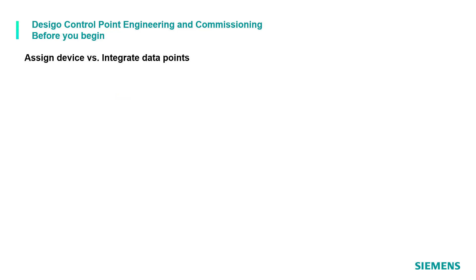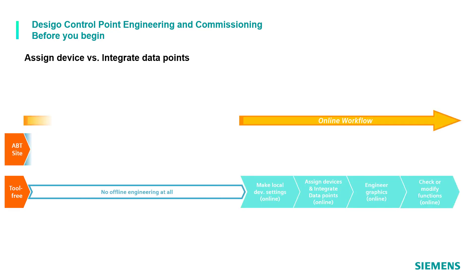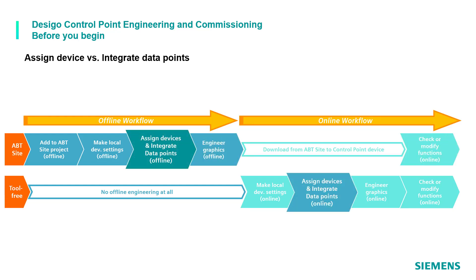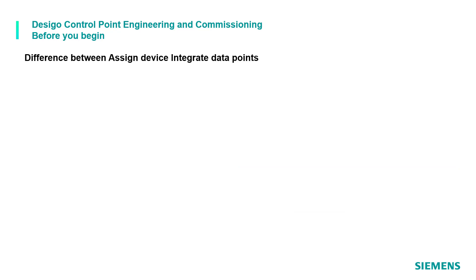In general, we distinguish between two main workflows for engineering: the tool-free workflow, which we can call the online workflow, and the engineering with ABT site, or offline workflow. In both cases, devices need to be assigned and data points need to be integrated. We are now going to learn the difference between assigning devices and integrating data points.